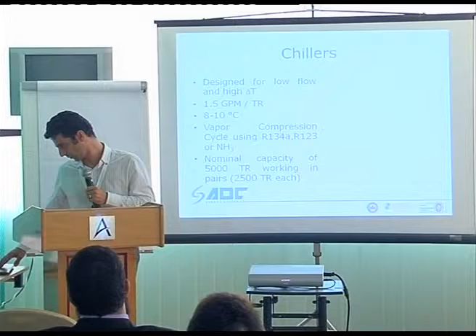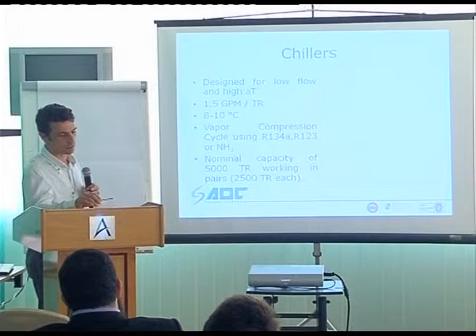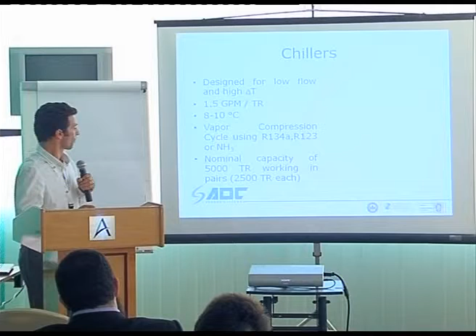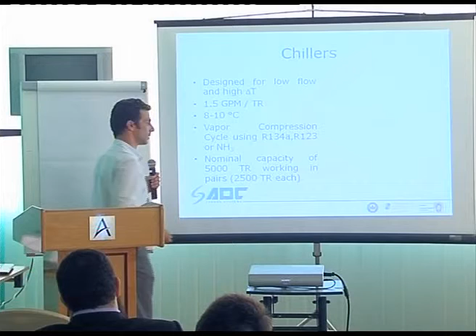Because of the plant and the capacity of the plant, definitely we go to the biggest and the largest capacities that we have in the market. You can go up to 7,000 tons in a single chiller these days. Siemens have produced a 10,000 ton single machine. These are quite large machines. They could be from here up to the end of this hall. But generally we tend to use the 2,500 ton of pairs of refrigeration of chillers. Right?